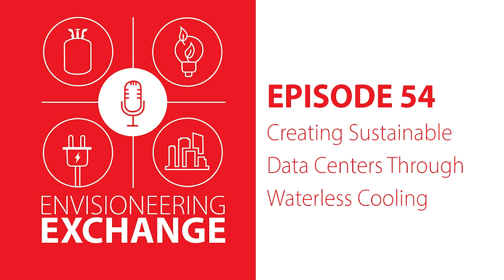Back in the day, when data centers were earlier in their evolution, water was not a major issue. Most data centers were in areas of municipal water. But when you get into 100 megawatt data centers, as is pretty typical today from a lot of the large hyperscalers, water use for evaporative cooling and other methods is still common, and it can be as much as 1.5 liters per kilowatt hour of data center operation.